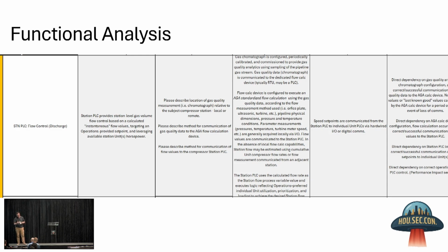If it's being communicated over the network to a smart valve that receives its command through a network interface, that's different than a solution that uses a 4 to 20 milliamp current loop to communicate that result. But understanding that change helps us account for that risk that we use in deciding how that's being solutioned out.